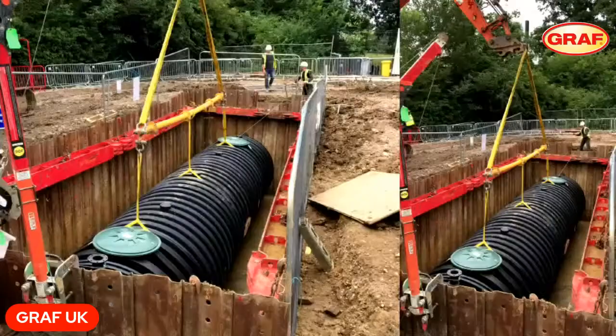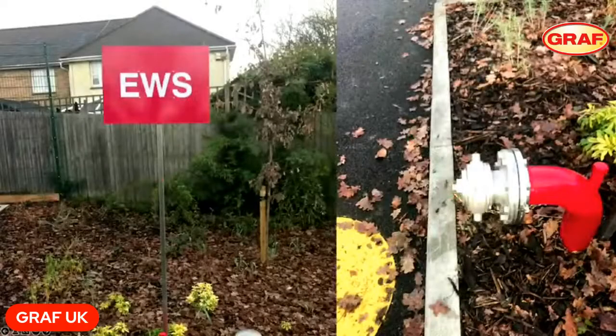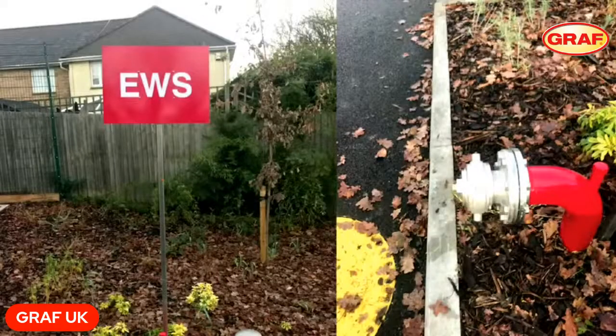Along with, of course, the tank itself, we have the accessibility down into the tank for maintenance and servicing. And we also have the signage and couplings available, which basically indicates that there is an emergency water supply available and local for the fire service to connect onto. Of course, it's going to be designed into the emergency service manual and the risk assessment, so the fire services know where it is. But it's also quite visually present in the images you can see now, and all systems here from us will come with the ability to have the UK connection point for the fire services, as well as the signage, not only the sign saying EWS for emergency water supply, but also the covers as well. So really it is a complete solution sold by Graf.